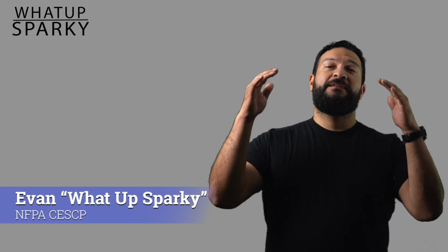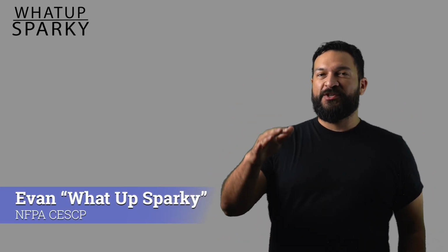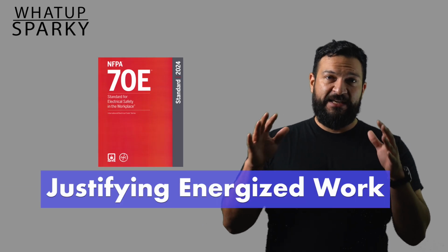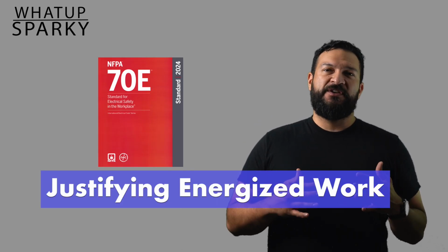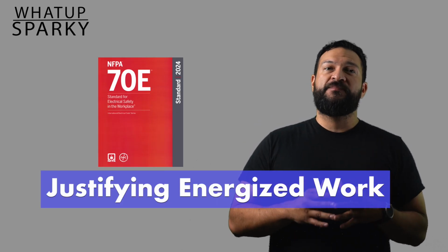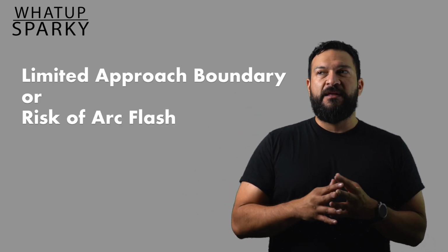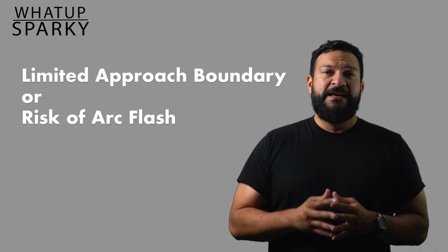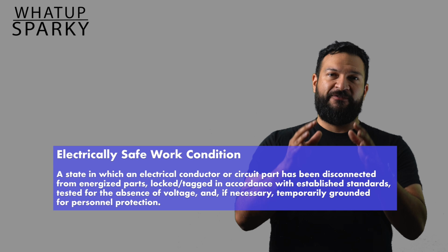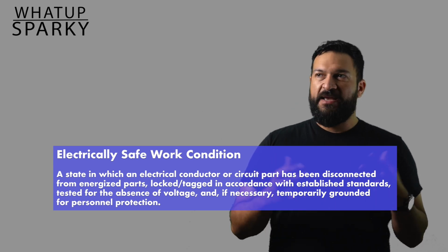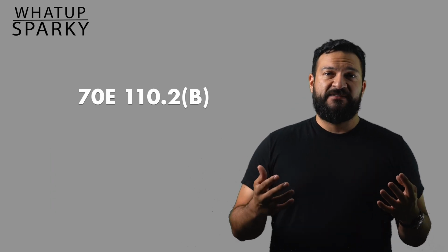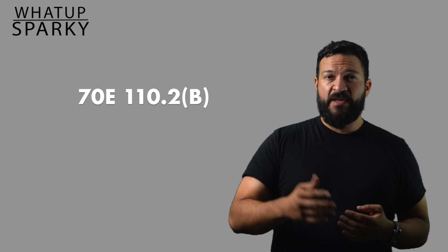What up? Let's talk about when energized work is actually allowed under the 70E. Now, we're not looking for excuses, we're aiming for clarity. So here's the deal. Anytime you're working inside the limited approach boundary or you're doing something that might cause an arc flash, that equipment is supposed to be in an electrically safe work condition. Basically, de-energized. That's the rule.